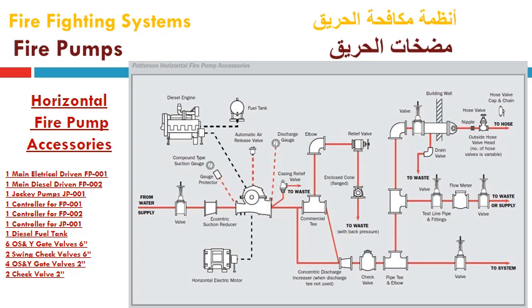To conclude, all the accessories should be added to the horizontal fire pump, starting from its driver. The pump is located here. It can be connected to a horizontal electrical motor, since it is a horizontal pump, or a diesel engine can be connected also. If we use a diesel engine, we will use a fuel tank to provide fuel supply and return for the diesel engine.